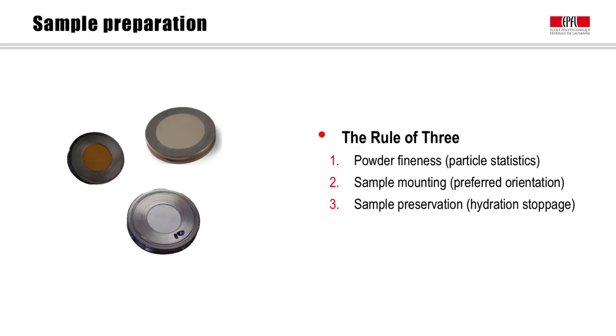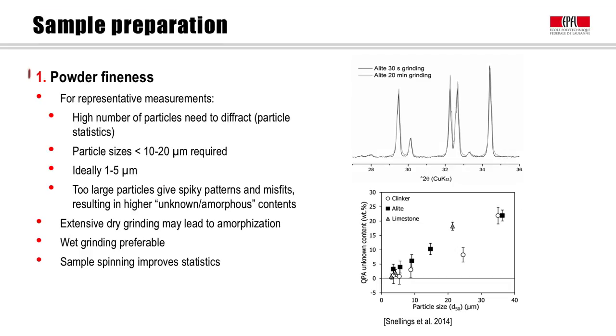Now looking at powder fineness in more detail, it is obvious that not only do we have to take a representative subsample, but we also need to make a powder which has a high number of particles that can diffract. If we have a powder with a large number of fine particles, we get a representative XRD measurement in which the peaks can be repeatedly measured. In practice, particle sizes of about 10 to 20 micrometers or less are required, ideally even smaller than 1 to 5 micrometers.